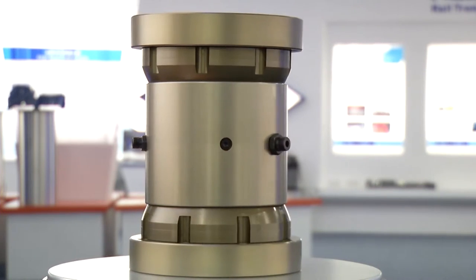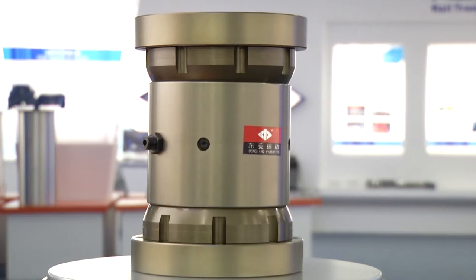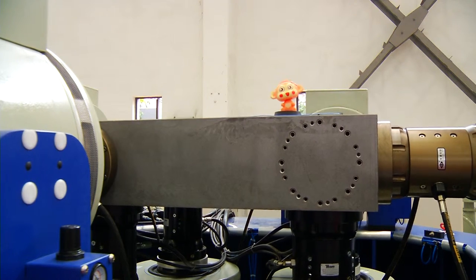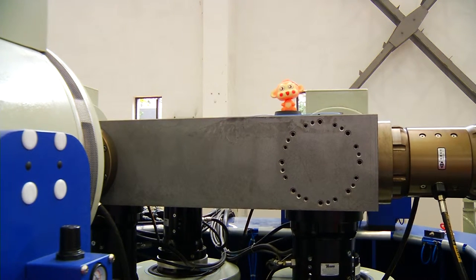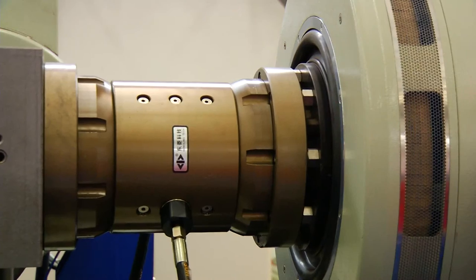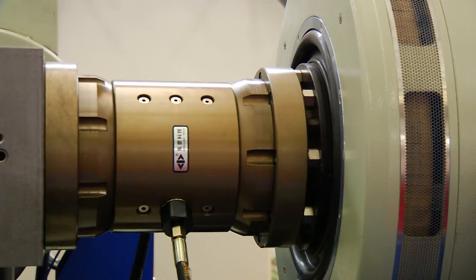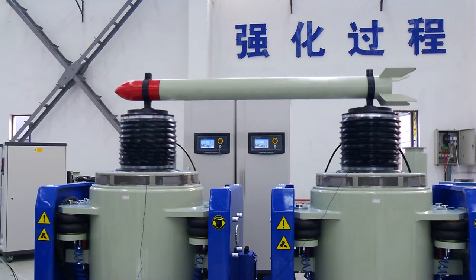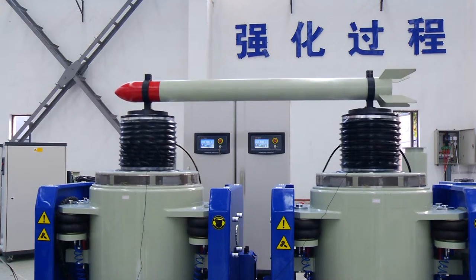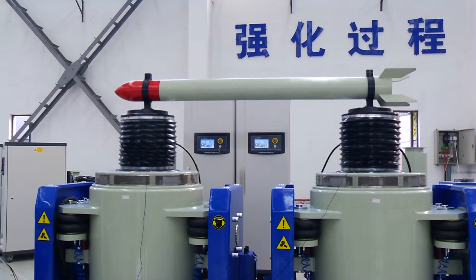Hydrostatic spherical coupling has large axis stiffness, high accuracy, and extra high frequency transfer rate. It can turn an angle within plus or minus 6 degrees and working frequency is up to 2000 Hz. It is the core device of dual shaker test system and 6 degree of freedom vibration system.